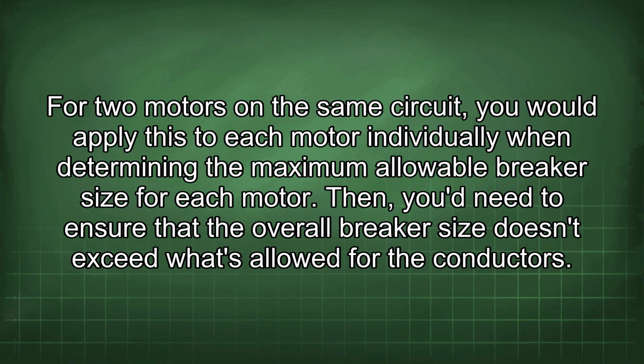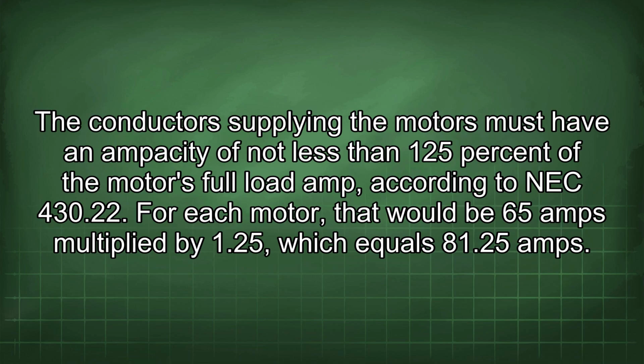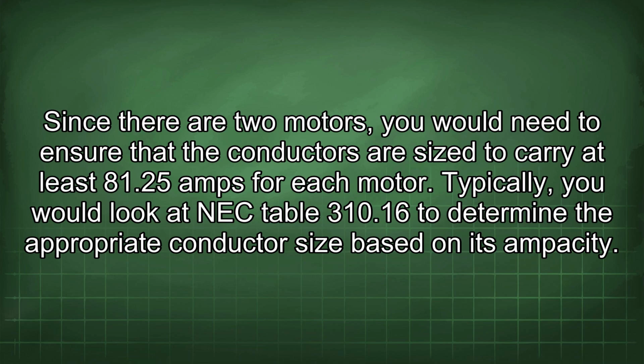Then, you'd need to ensure that the overall breaker size doesn't exceed what's allowed for the conductors. The conductors supplying the motors must have an ampacity of not less than 125% of the motor's full load amp, according to NEC 430.22. For each motor, that would be 65 amps multiplied by 1.25, which equals 81.25 amps. Since there are two motors, you would need to ensure that the conductors are sized to carry at least 81.25 amps for each motor. Typically, you would look at NEC Table 310.16 to determine the appropriate conductor size based on its ampacity.